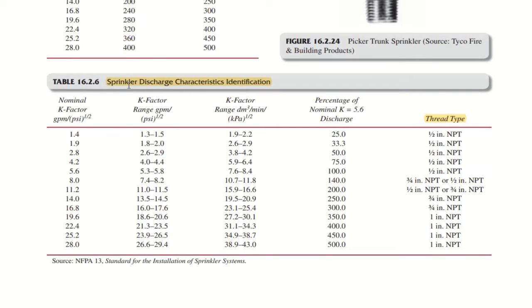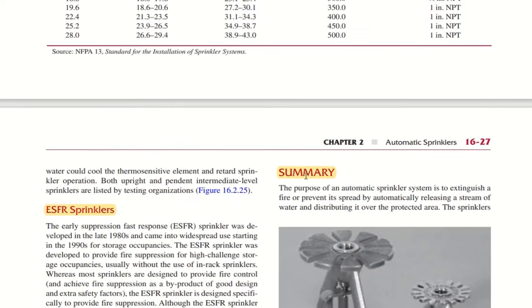Here you have one more table, sprinkler discharge characteristics identification. Here you have the K factors, and the percentage of nominal K equal to 5.6 discharge. At 5.6, the orifice size, or thread size, is half inch, so half inch NPT up to 5.6 K factor. For K factor 8 and 11.2, you might go ahead with 3/4 inch NPT or half inch NPT. In both cases you have sprinklers with K factor 8 with 3/4 inch NPT or half inch NPT. This is based on the manufacturer. So this is also an important table.